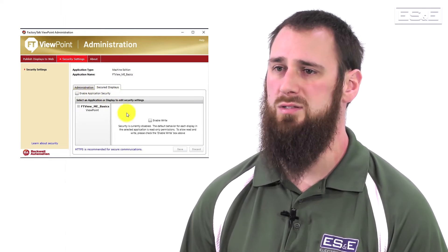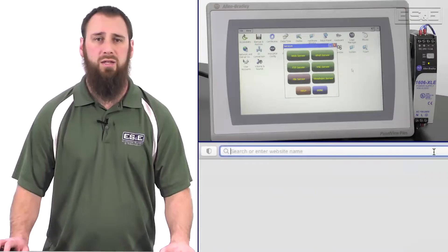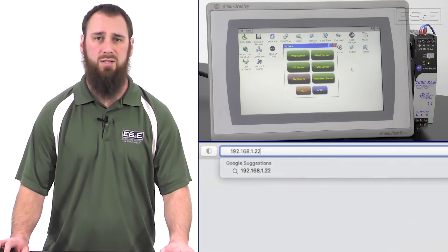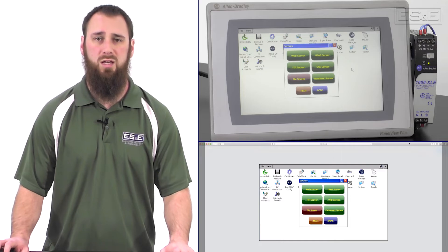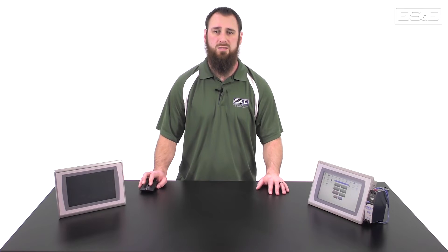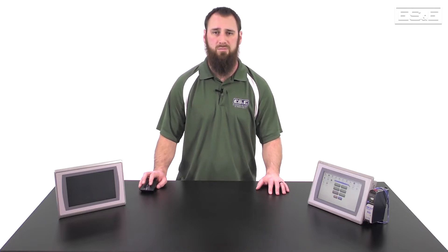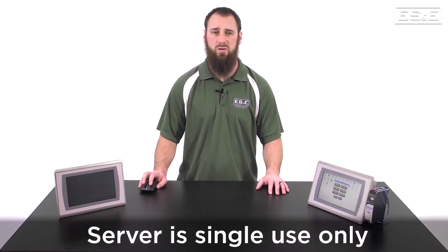When making the screens, you can choose if you want control or view only from the web browser. In the ME application, you can choose what you want to publish to a URL address, and as long as you are on the same network as that PanelView, you can type in the IP address and it will open up the graphics for you. This can act as a SCADA or reporting system for your local equipment that you will build within the FTView ME and can access in almost any browser. The main limitation is that only one person can connect to the Viewpoint server at any time.